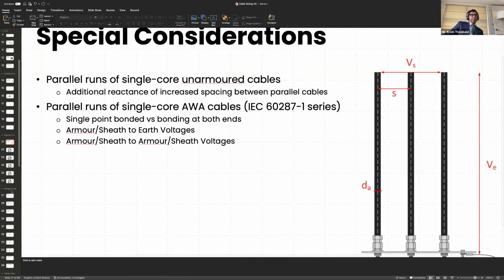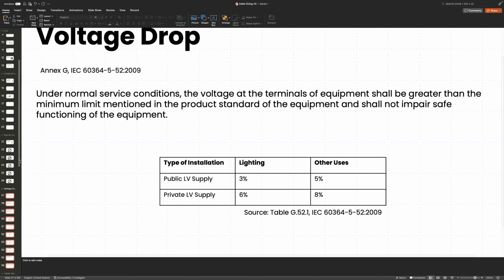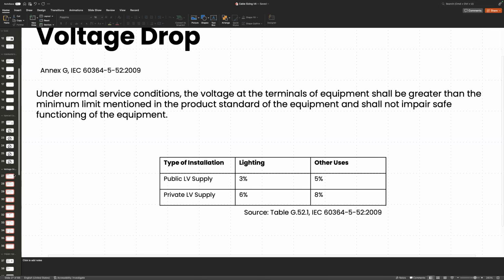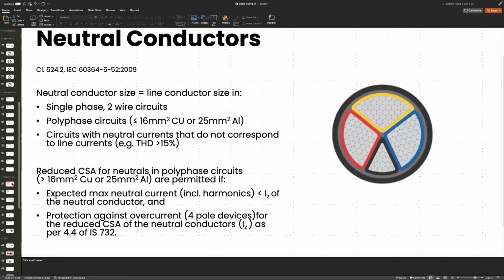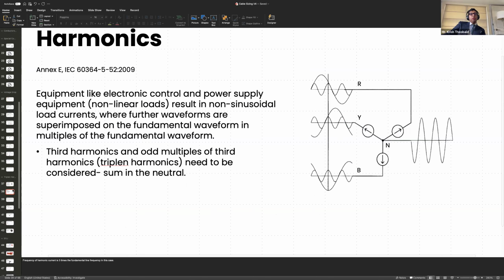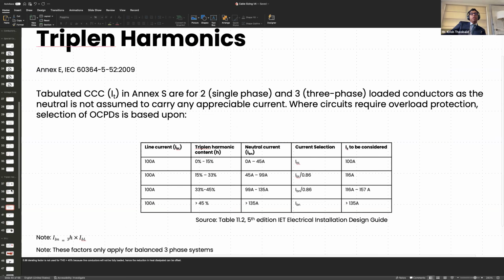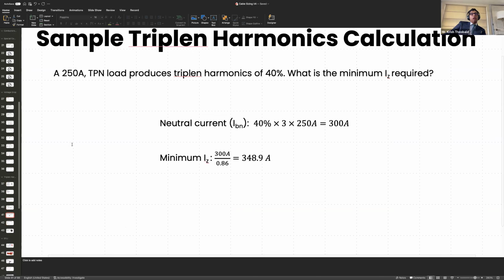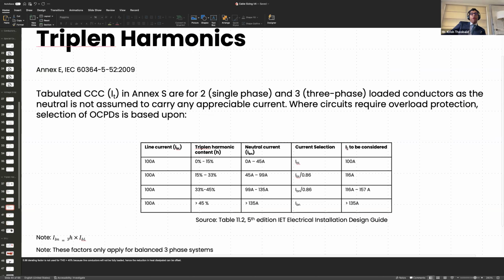I will combine all the questions together. Should we multiply the harmonic reduction factor along with the other derating factors? How to evaluate the harmonic current at design stage? How does harmonic current affect selection of OCPD? Okay. Should we multiply the harmonic reduction factor with other derating factors? Yes, of course, because this is to be considered for IZ. So yes, absolutely. You need to take it into account along with all other derating factors.